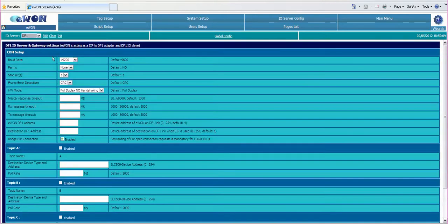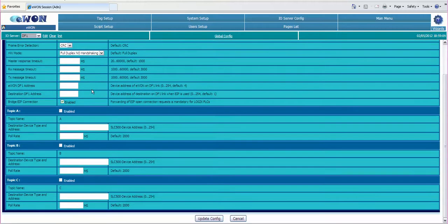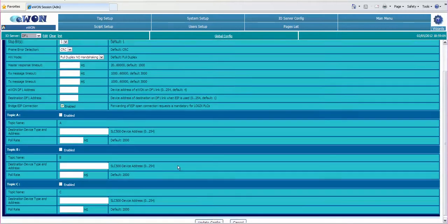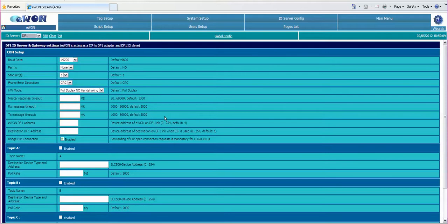Here we want to set up the COM setup in this case for 19.2 for the baud rate CRC full duplex no handshaking. When you do make changes make sure you click on the update config button down below. This takes care of the RS-232 DF1 connection.